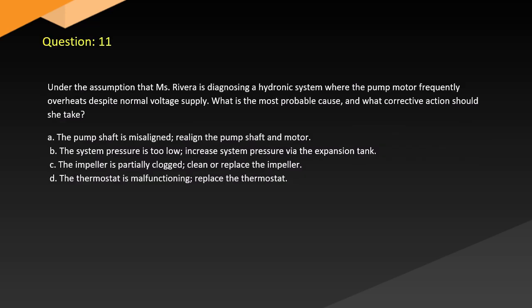Question 11. Under the assumption that Rivera is diagnosing a hydronic system where the pump motor frequently overheats despite normal voltage supply, what is the most probable cause and what corrective action should she take? A. The pump shaft is misaligned. Realign the pump shaft and motor. B. The system pressure is too low. Increase system pressure via the expansion tank. C. The impeller is partially clogged. Clean or replace the impeller. D. The thermostat is malfunctioning. Replace the thermostat.